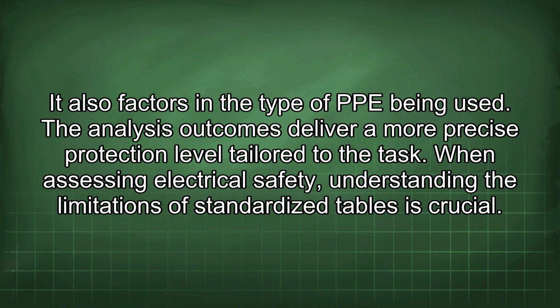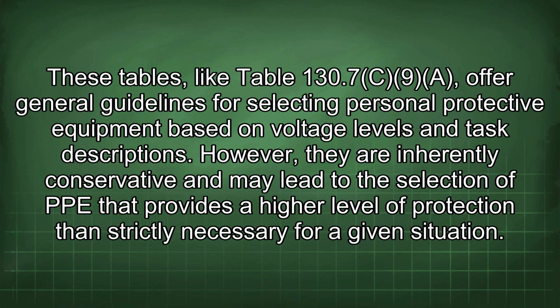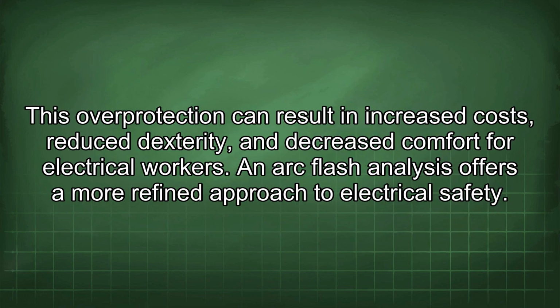When assessing electrical safety, understanding the limitations of standardized tables is crucial. These tables, like Table 130.7c9a, offer general guidelines for selecting personal protective equipment based on voltage levels and task descriptions. However, they are inherently conservative and may lead to the selection of PPE that provides a higher level of protection than strictly necessary for a given situation. This overprotection can result in increased costs, reduced dexterity, and decreased comfort for electrical workers.